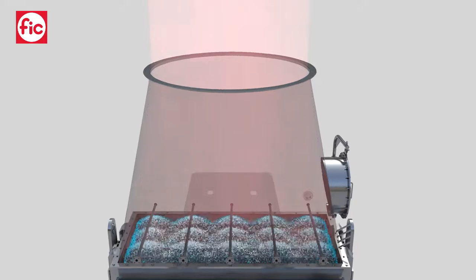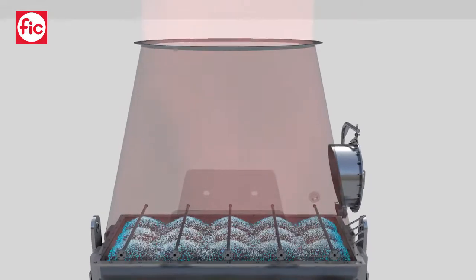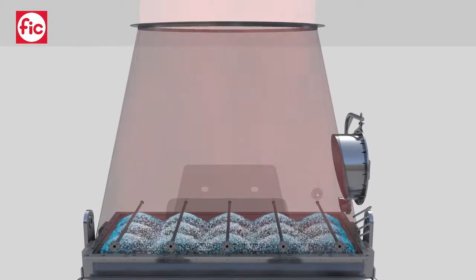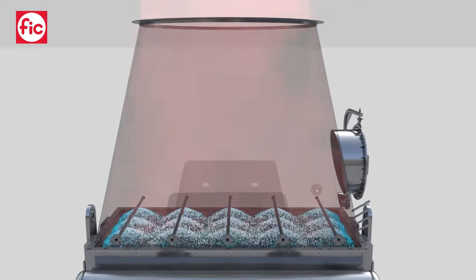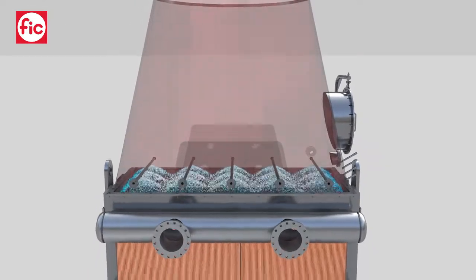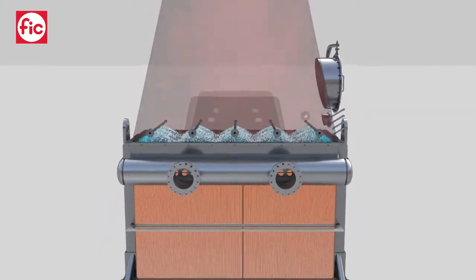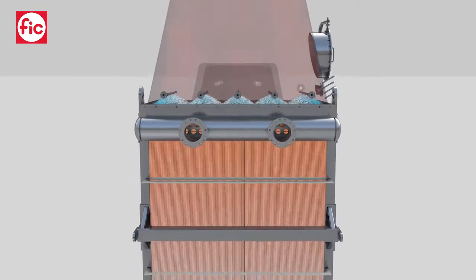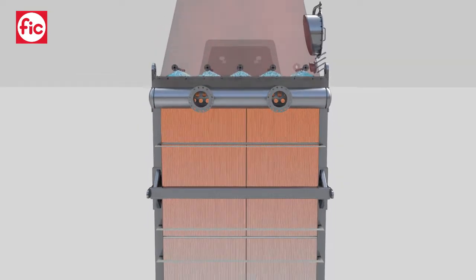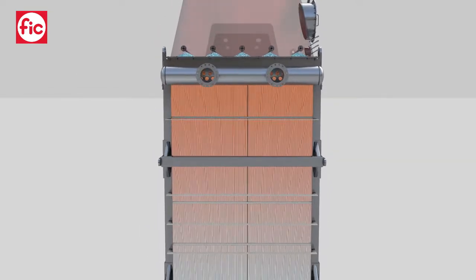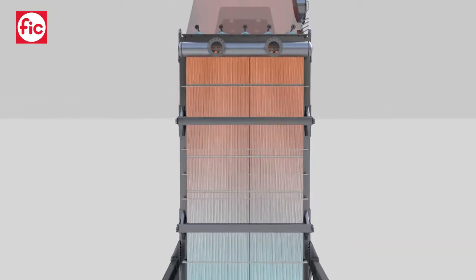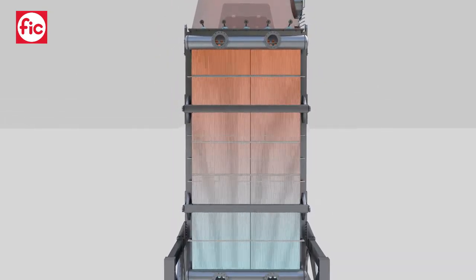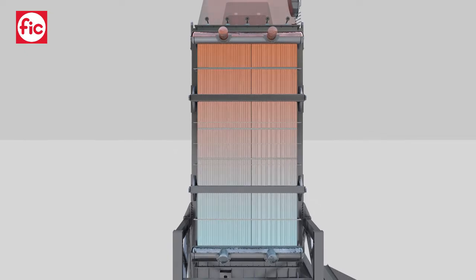The flue gas enters from the inlet hood on top. It is distributed across the whole section, saturated and cleaned. Afterwards it enters the heat exchanger and flows between the plates. Water flows inside them in a counter-current process.